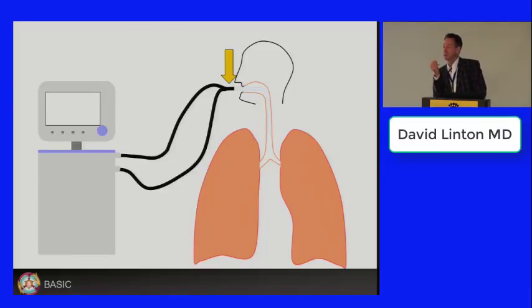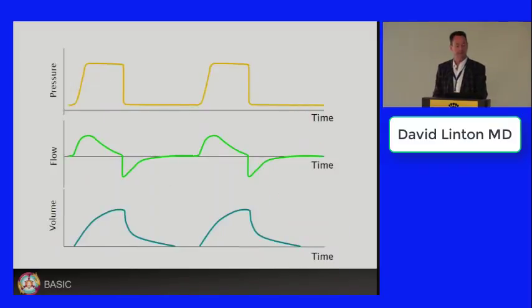The problem is, where are you measuring that pressure? Do you know that some machines are measuring the pressure inside the machine, some are measuring it as it comes out the machine, some are measuring it at the patient's end, like this picture says, and some are extrapolating it from what's coming out the lungs and what the pressure is at the end of expiration. So every ventilator is doing it differently.